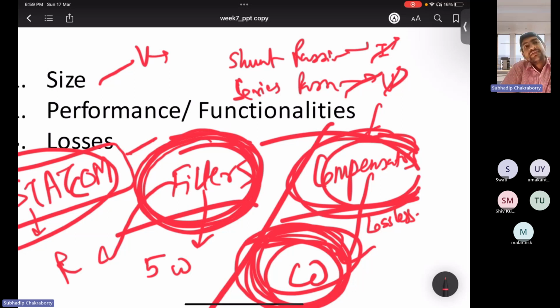But compensators, the functionalities are completely different. With control, we just mitigate for that harmonic component. We do not filter anything out. We just extract harmonic content and then tell the DStatCom or some active devices to feed in that harmonic components. It is not eliminating anything. So those two things are different.